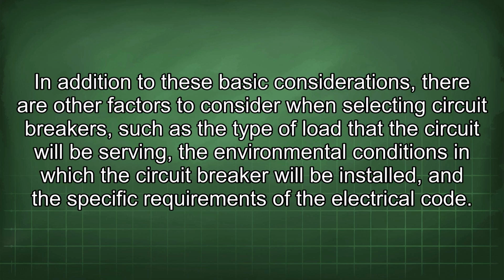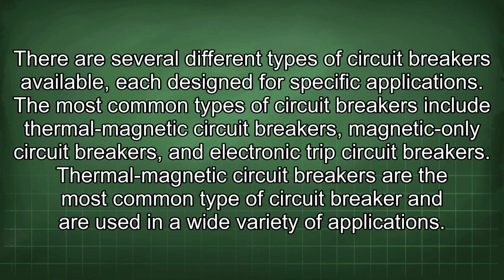In addition to these basic considerations, there are other factors to consider when selecting circuit breakers, such as the type of load that the circuit will be serving, the environmental conditions in which the circuit breaker will be installed, and the specific requirements of the electrical code. There are several different types of circuit breakers available, each designed for specific applications. The most common types of circuit breakers include thermal magnetic circuit breakers, magnetic-only circuit breakers, and electronic trip circuit breakers.